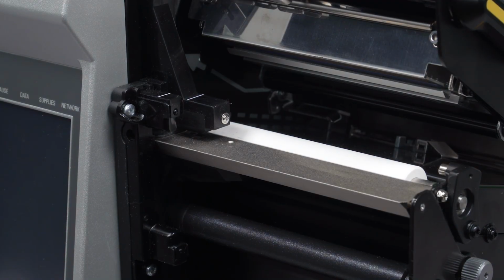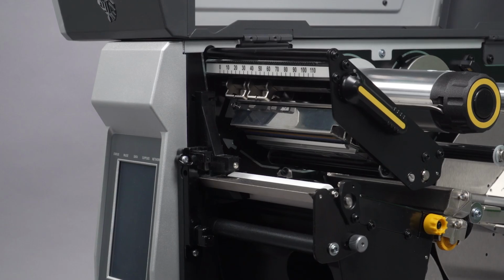If there is a label jam or adhesive buildup, repeat the cleaning with a new cloth or swab until all leftover adhesive and debris are removed. Gently blot away any debris with the cloth or swab and the isopropyl alcohol. Do not scrub the Platen Roller as this can damage its surface. Allow at least 30 seconds for the Platen Roller to completely dry. Close the printhead assembly.